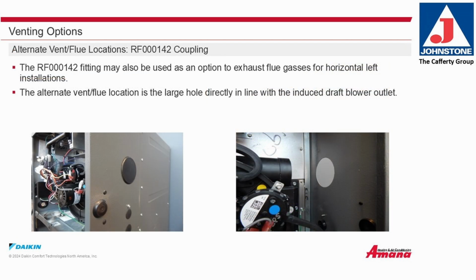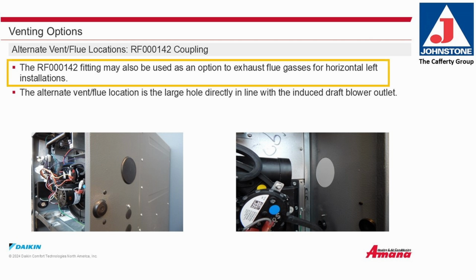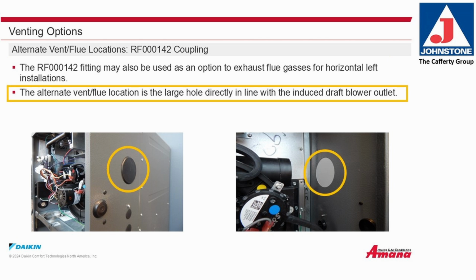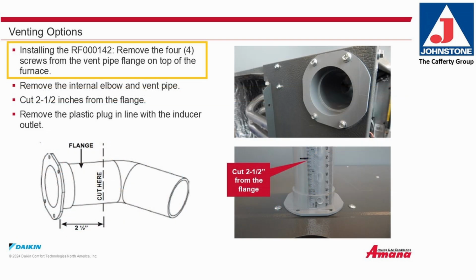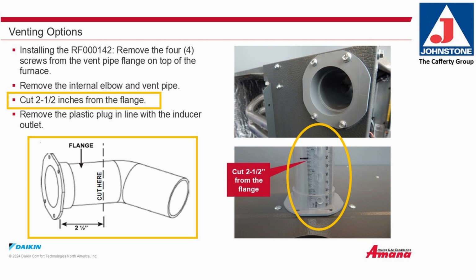Venting options. Alternate vent flue locations, the RF000142 coupling. The RF000142 fitting may also be used as an option to exhaust flue gases for horizontal left installations. The alternate vent flue location is the large hole directly in line with the induced draft blower outlet. Installing the RF000142: remove the 4 screws from the vent pipe flange on the top of the furnace. Remove the internal elbow and vent pipe. Cut off the pipe 2.5 inches from the flange.